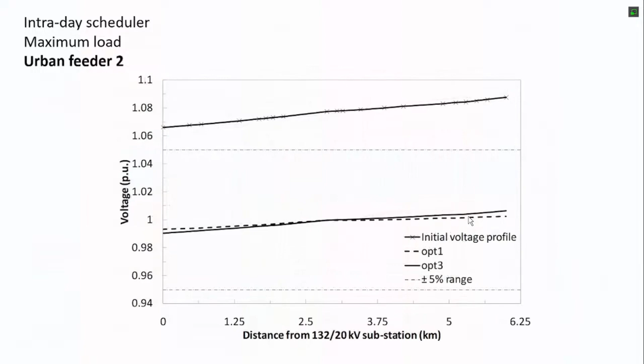For urban feeder 1, urban feeder 2 practically has the same behavior, and this is for rural feeder 1. Originally, without the intraday optimization, the voltage in some of the buses, where the x-axis shows the distance from the substation along the radial feeder configuration, is too high with respect to the rated value. After the optimization, this goes down, so the optimization is able to restore the voltage all along the line to stay inside the band. The same behavior is seen for the second rural feeder.